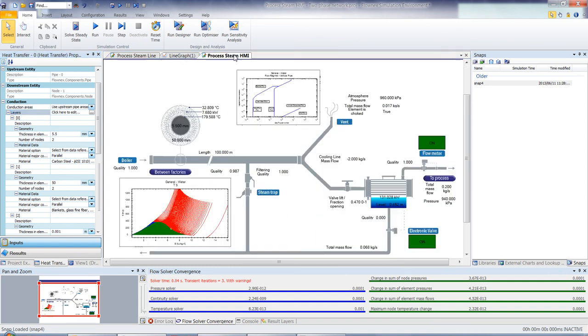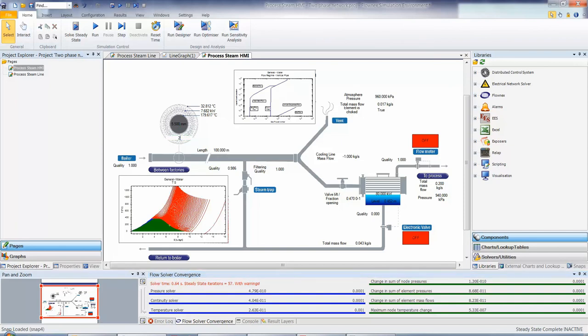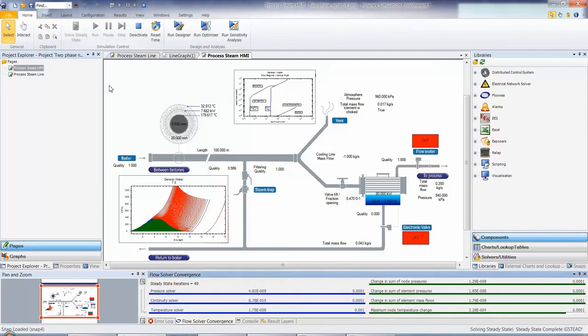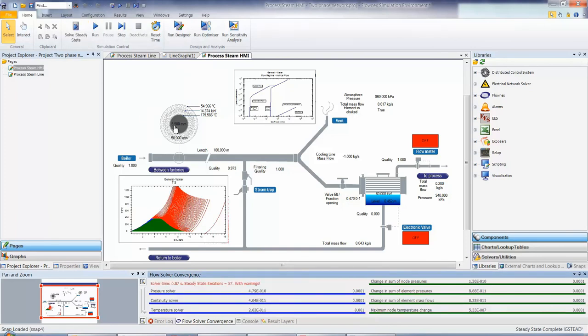So let's have a look at our process HMI at what we're modeling. So initially we designed the system to run at around 50 millimeter insulation and give us a surface temperature of 32 degrees Celsius, which is quite good. So if we go ahead and change that insulation thickness in Flownex from around 50 millimeters to, let's say, 20 millimeters, we can then see the effect if we solve it in steady state. So now we have a case where we don't have an acceptable surface temperature of 32 degrees. It's gone up to around 55 degrees. And we can then use tools in Flownex to design the optimum cladding and insulation thickness to give us the temperature that we do require. In this case, we're just going to keep it around 50 because 32 degrees is quite acceptable.